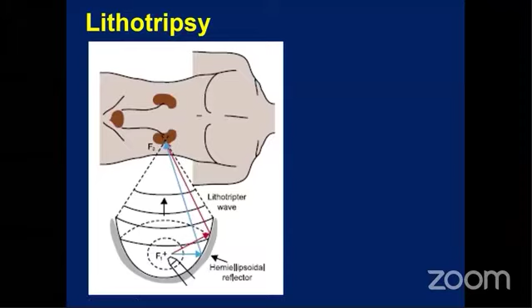And here are some examples of artificial stone damaged by cavitation. Here's another example of the cavitation in shockwave lithotripsy on a target stone. Here in the lab, the problem begins to be clear. You see these bubbles aren't on the surface. And what that does when they collapse is it damages the surrounding tissue. So one of the problems with shockwave lithotripsy is what they call collateral damage. Here's another example of a stone with bubbles which are presumably damaging the surrounding tissue. But it's also possible to get around that.